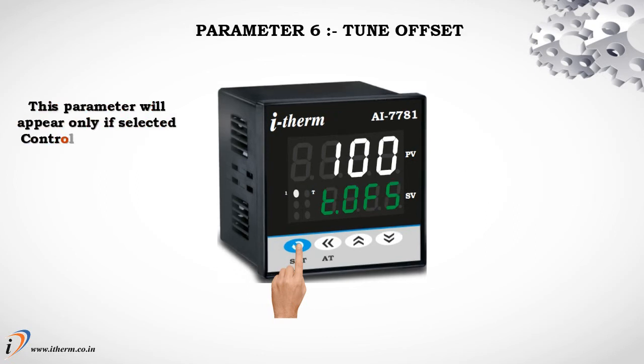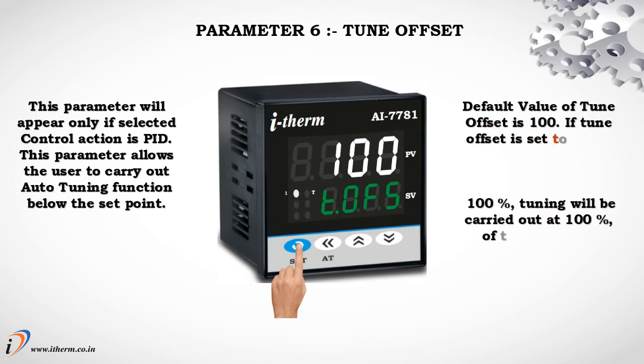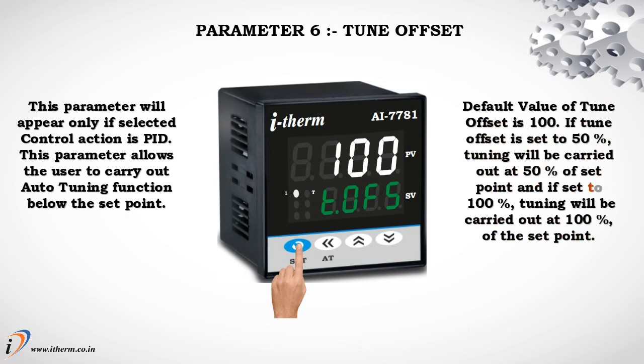Parameter 6 is Tune Offset. This parameter will appear only if the selected control action is PID. It allows the user to carry out the Auto-Tuning function below the set point. The default value of Tune Offset is 100. If set to 50%, tuning will be carried out at 50% of the set point; if set to 100%, tuning will be carried out at 100% of the set point.